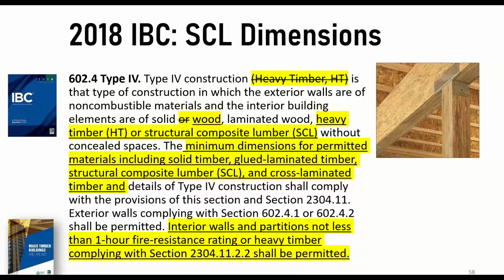So there was a proposal, G178, that makes it clear that structural composite lumber should be considered equal or equivalent to heavy timber, and it clarifies the appropriate distinctions between nominal dimensions, net finish dimensions, and actual dimensions for things like heavy timber, glulam, structural composite lumber, and cross-laminated timber. So you can see in the highlighting there, we're looking at minimum dimensions for materials, glulam, structural composite, and CLT. As long as they have those minimum requirements and meet those minimum fire resistance ratings, you can use them.